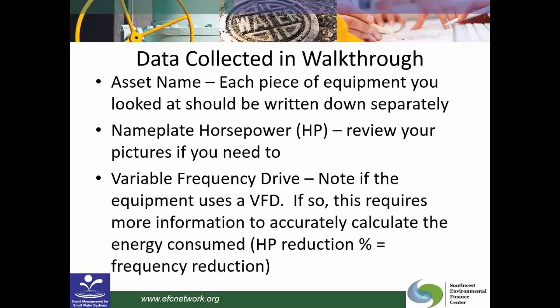So the data that you've collected in the walkthrough should be input into your spreadsheet, and you want to make sure that you give each asset a unique identifying name and ID number. You want to make sure that you've gotten the nameplate horsepower documented. And again, the pictures can come in handy here if you need to double check.